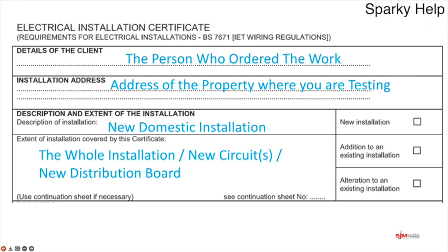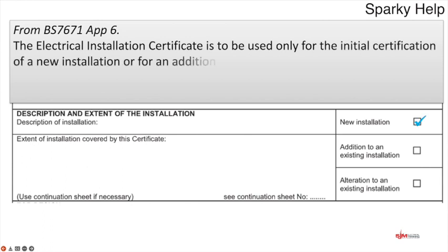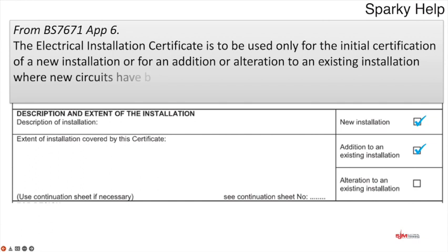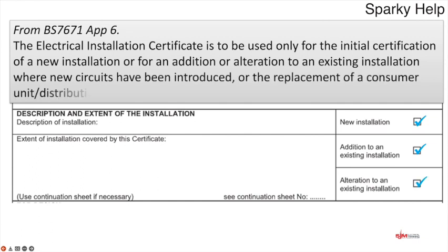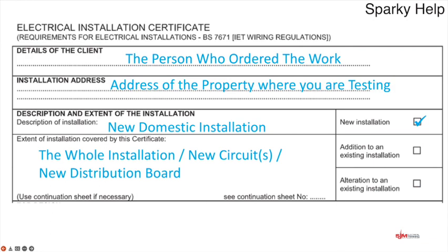What do we need to put in? Well, if we look at BS 7671, it tells us what we should be putting in. From BS 7671, Appendix 6, it says the electrical installation certificate is used only for initial verification of a new installation, for the alteration or addition to an existing installation, or where new circuits have been introduced, or the replacement of a consumer unit/distribution board. So each of those, whichever it happens to be, you tick off. Hopefully as you were watching that, it was ticking it off for you. So we're going to base this, as we said already, on a new installation, so we'll just leave that particular one ticked.